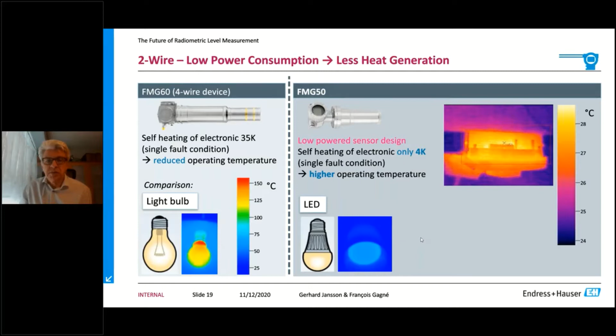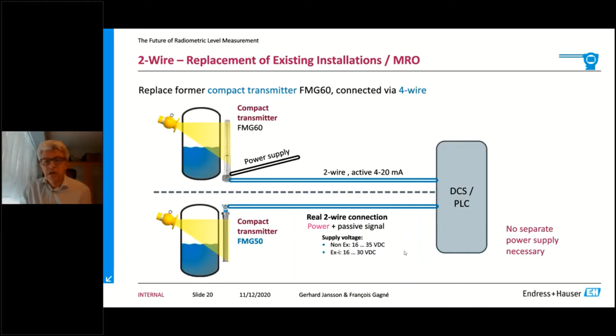So this is how we did it in the past. We had a 4-wire connection, power supply, 4-20. This would be an active output in that case. If we now look to a loop powered setup, this is of course now passive. It's only a 24-volt power supply, getting back the 4-20 milliampere signal. So if you're going from one to another, you need to change the input from an active input to a passive input on the PLC or the DCS. No additional power needed, so once again, a lot of cost savings there.